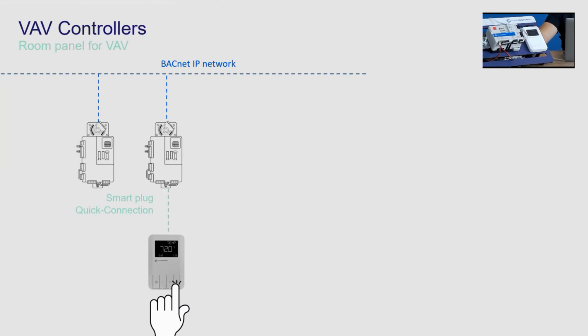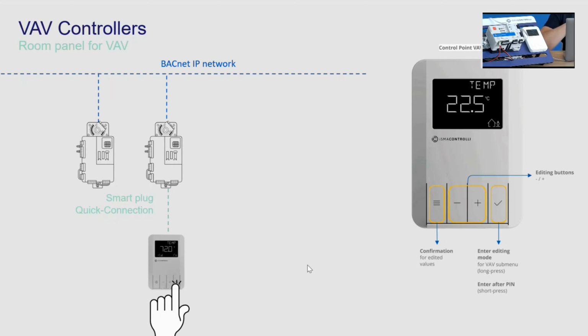screen now. So what we have now, we have a single VAV controller connected directly using the smart plug, which is our quick connector that shares both the power and communication. As the control point itself, it's also BACnet MSTP. It communicates and allows us to configure one-to-one the VAV controller on the network. So let's look at the buttons that we have available on the panel itself.